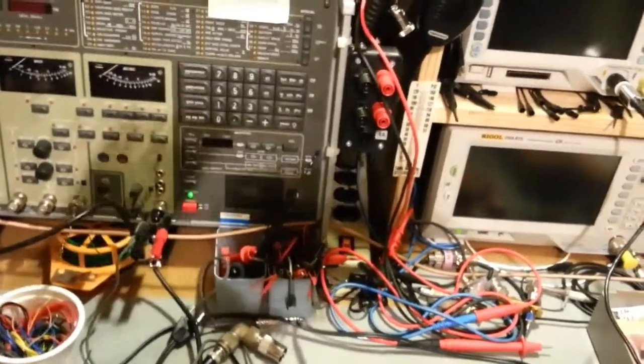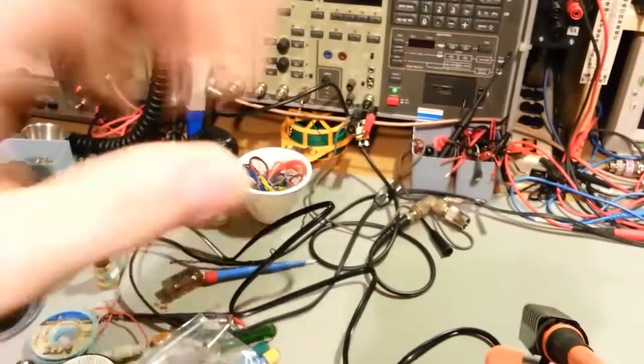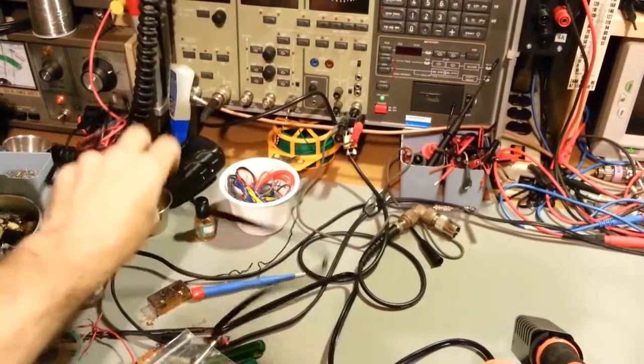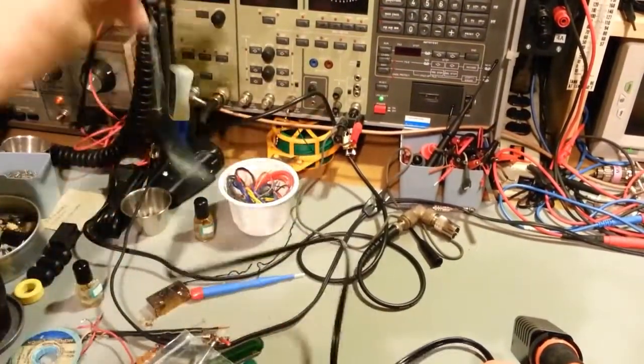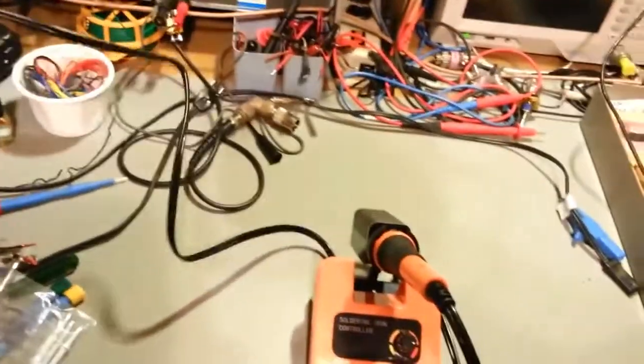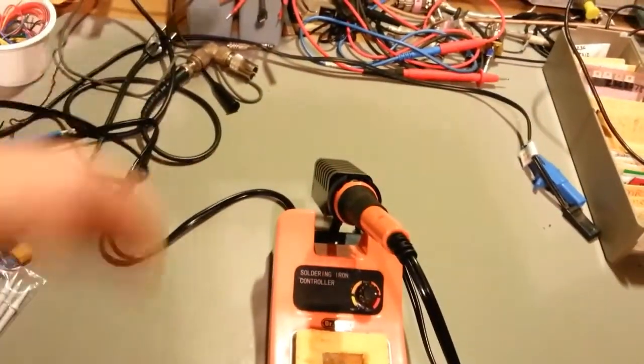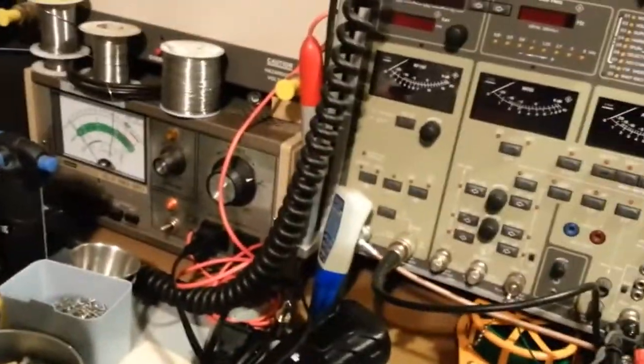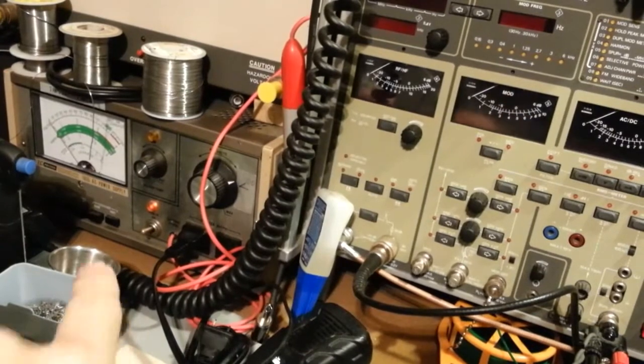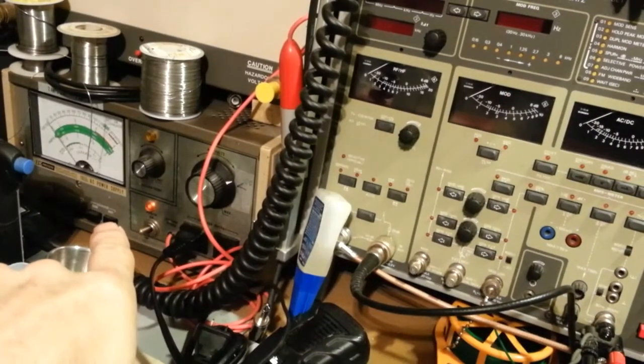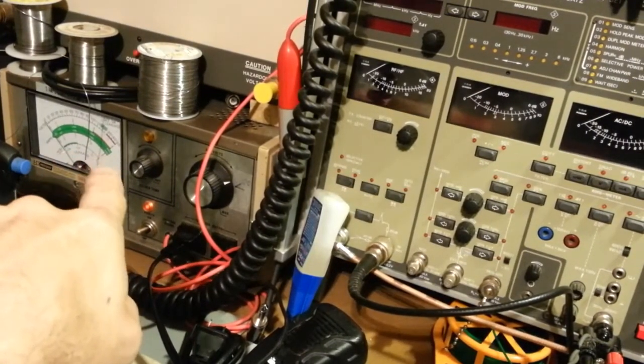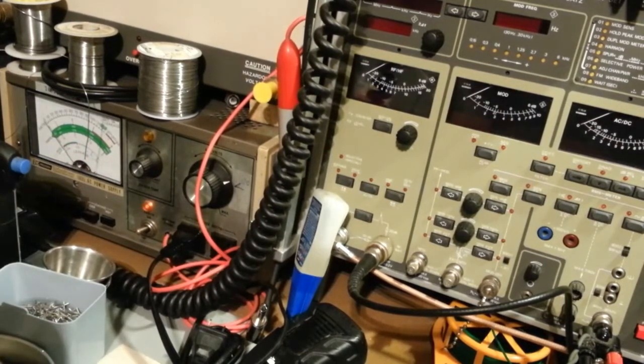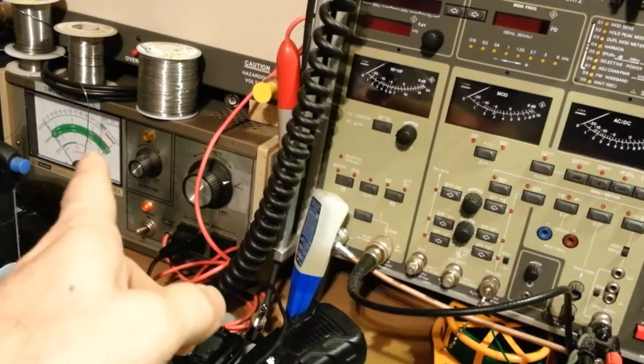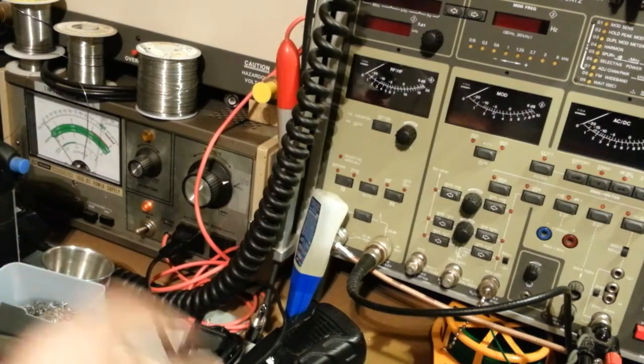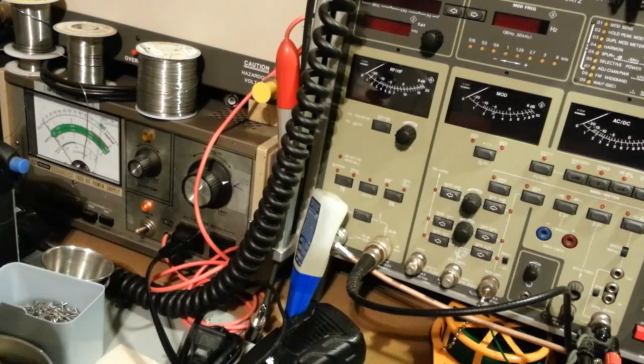Just so you can see on one picture, there's the isolation transformer. Here's the power cord plugged into the isolation transformer, and you can see that comes down to the soldering iron stand. So what we're going to do is focus on that button down there. I have it pressed in right now, it's on hot. The leakage scale is on the bottom. What you want to see is below 500 microamps, not milliamps, microamps.